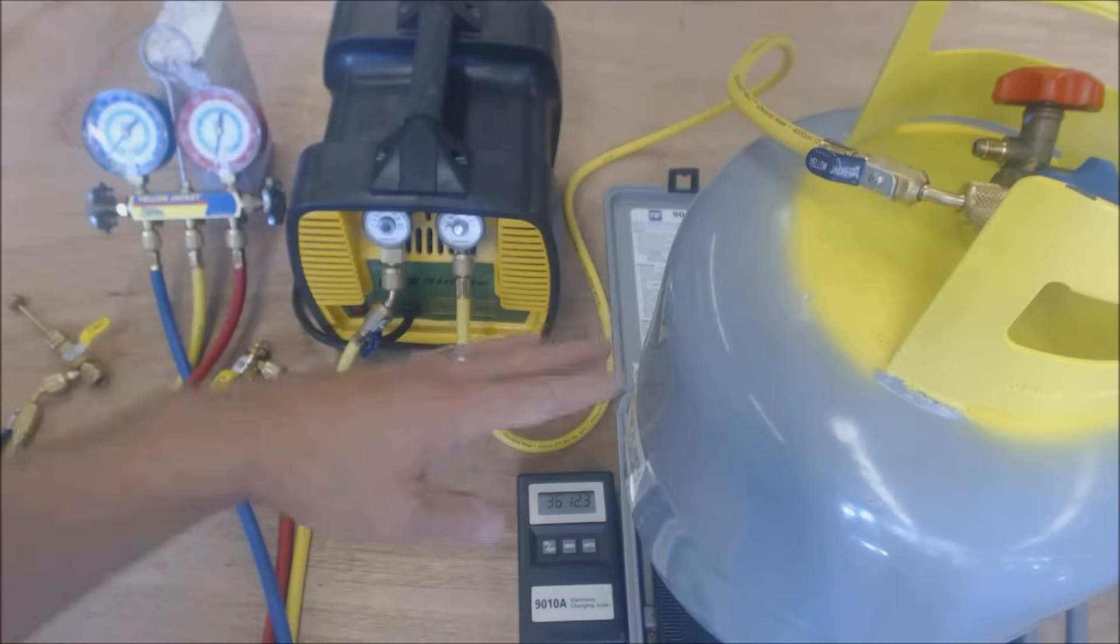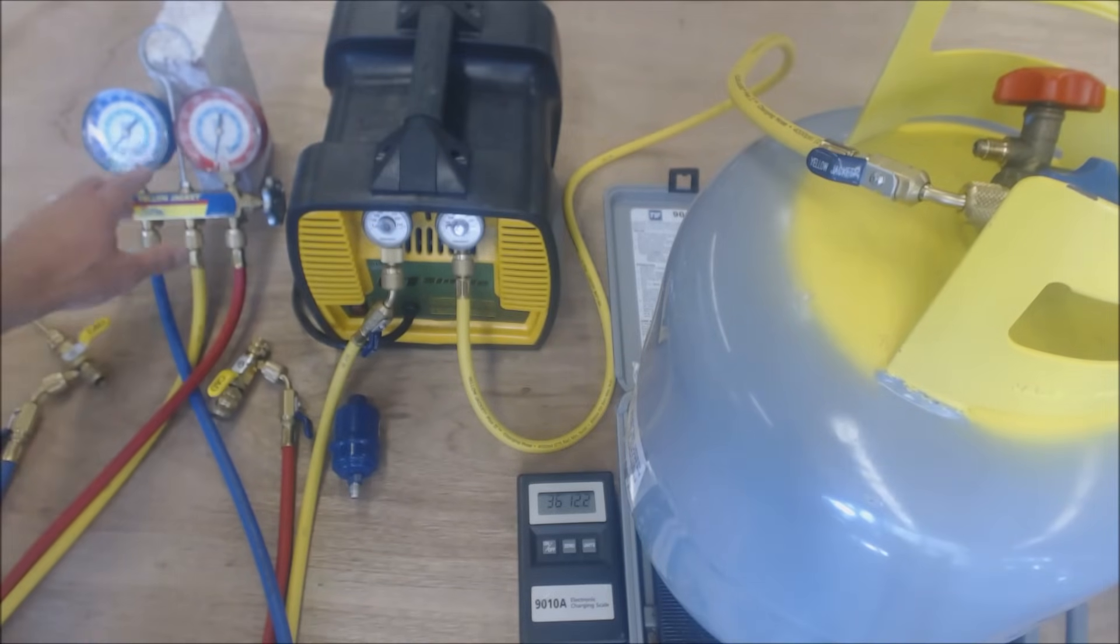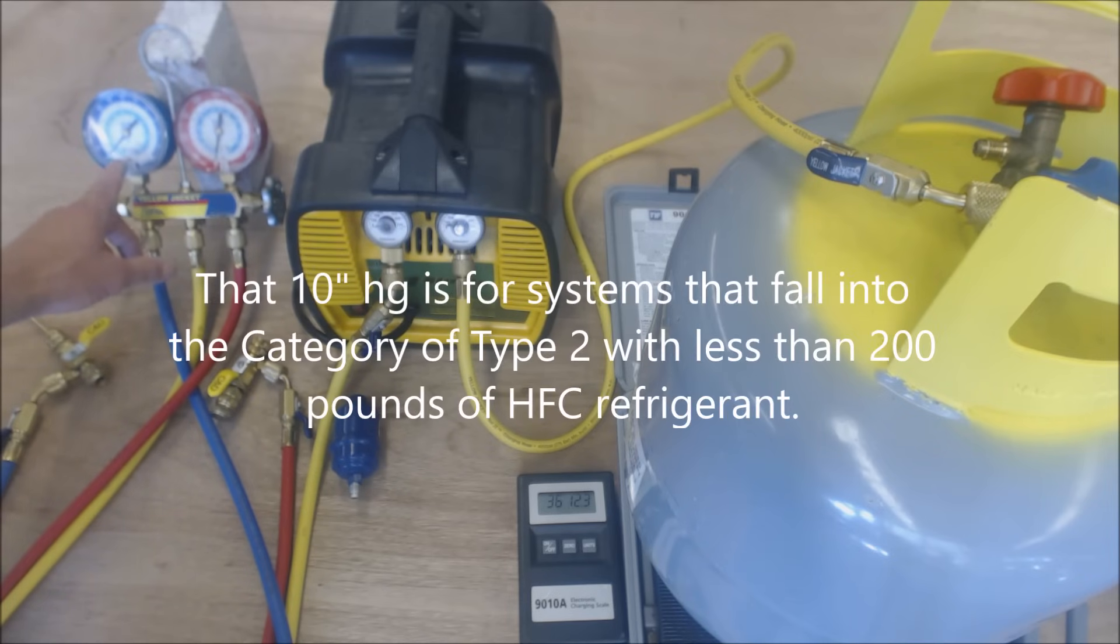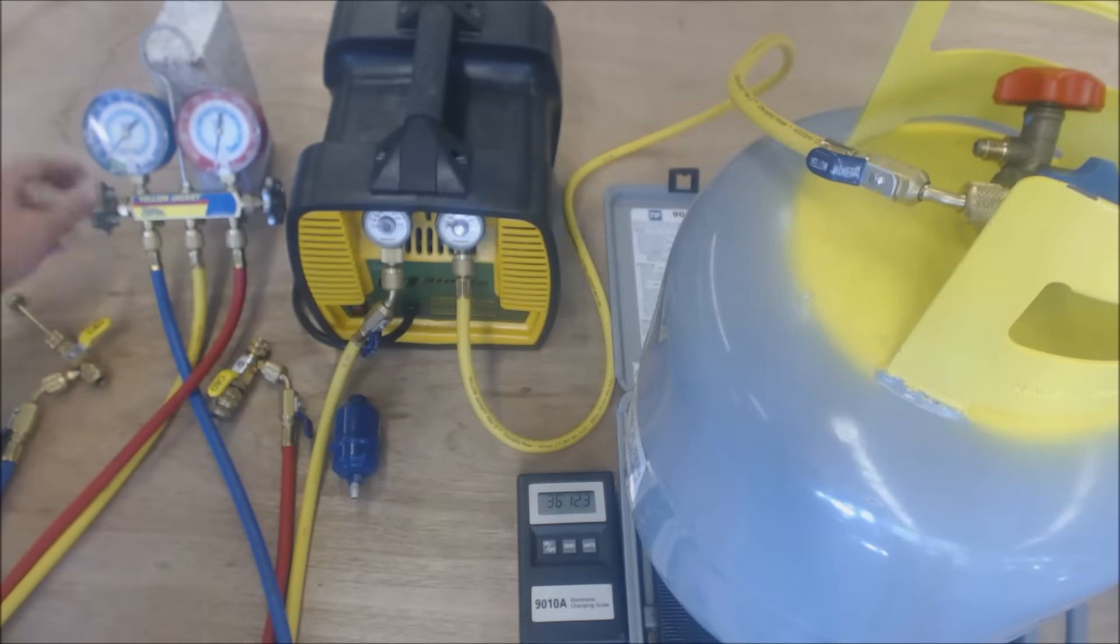Since this is 134A refrigerant that we're dealing with here, when we recover the refrigerant out of the system, we're going to end up recovering it down to 10 inch Hg—down into the green. We need to be able to hold that. So basically while the recovery system is running and it's putting refrigerant into the bottle, we can just close this handle down temporarily just for half a second and just check to see where this needle rises up to. If it rises up past 10 inch Hg, we're just going to open it and continue to let it suck down to 10 inch Hg.